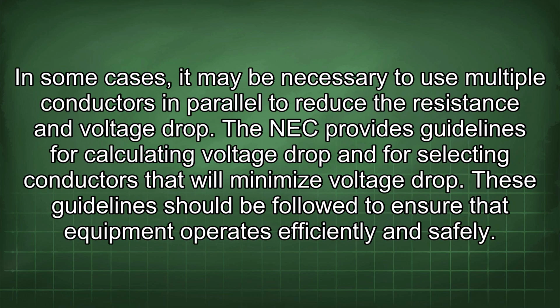In some cases, it may be necessary to use multiple conductors in parallel to reduce the resistance and voltage drop. The NEC provides guidelines for calculating voltage drop and for selecting conductors that will minimize voltage drop. These guidelines should be followed to ensure that equipment operates efficiently and safely.